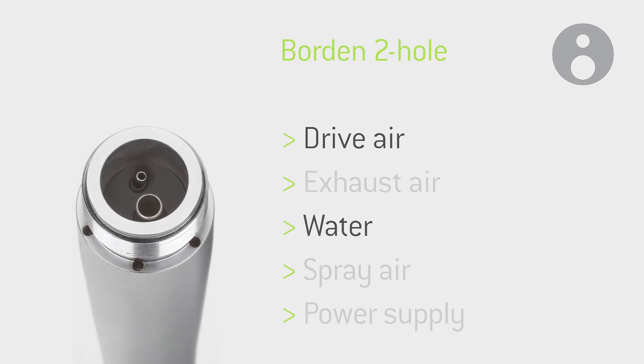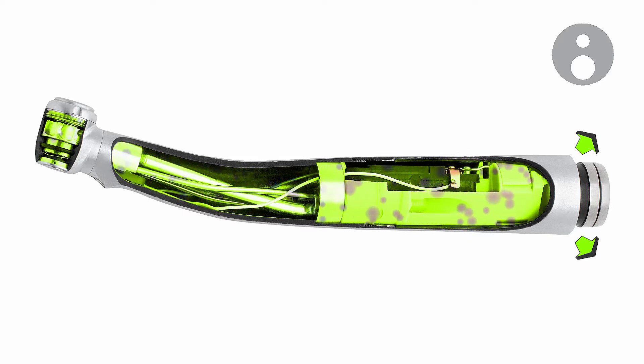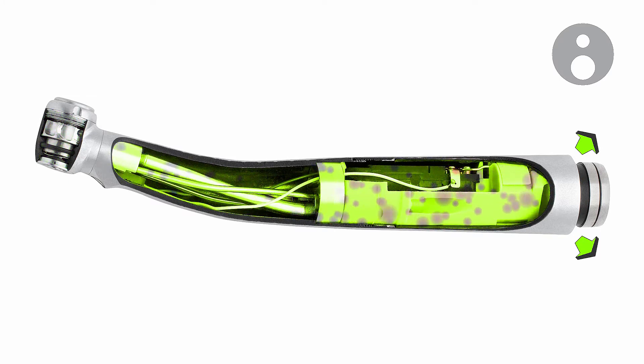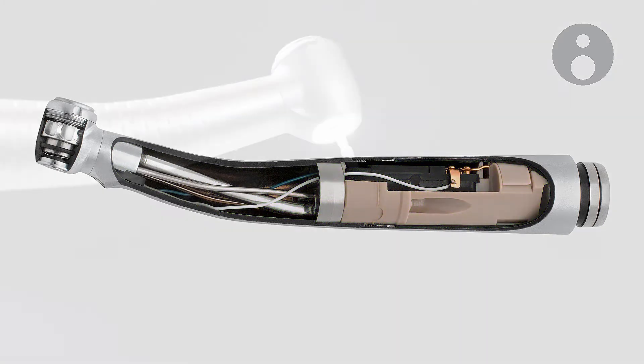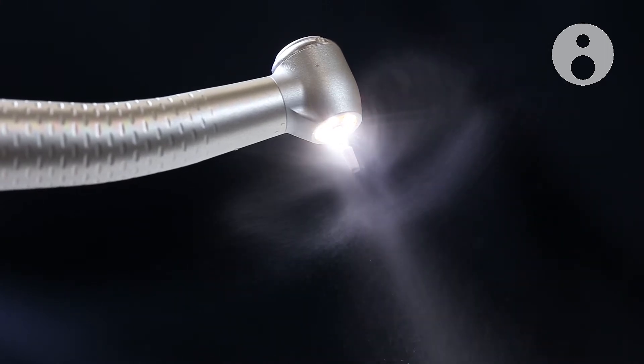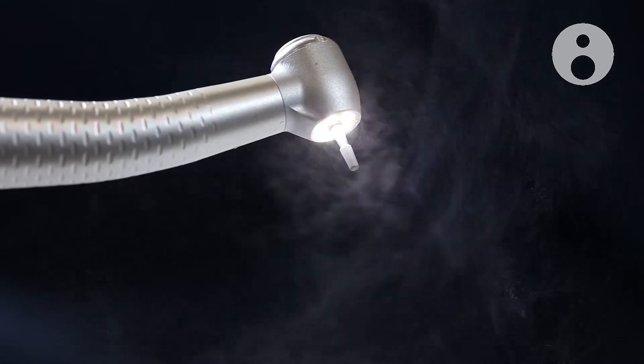The Borden two-hole connection has one connection each for the drive air and the coolant. The disadvantage is that the exhaust air from the rotor escapes on the connection side of the turbine or air motor and is not fed back into the dental unit via the supply line, meaning this air can be felt on the user's hand. The air required for cooling is diverted from the drive air within the instrument, which lowers the pressure and cannot be controlled separately.